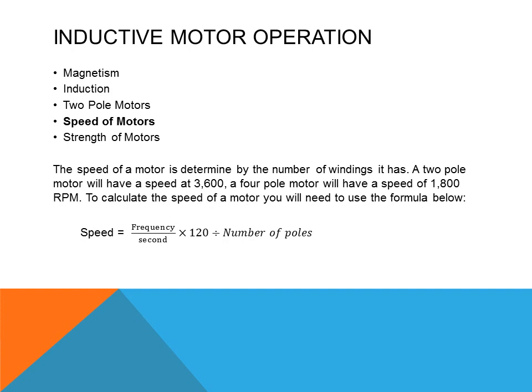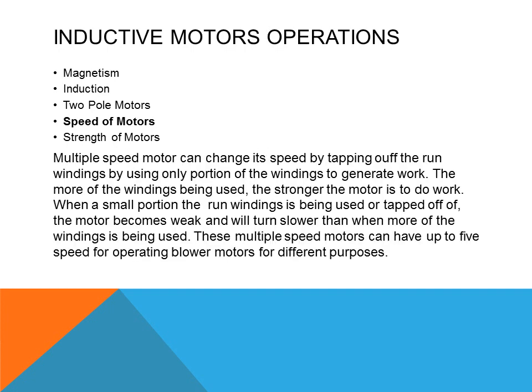The speed of a motor is determined by the number of poles it has. A two-pole motor will have a speed of 3,600 RPM, while a four-pole motor will have a speed of 1,800 RPM. To calculate the speed of a motor, use the formula: speed equals frequency divided by seconds, times 120, divided by the number of poles. Multiple speed motors can change speeds by tapping off the run windings — using only a portion of the windings to generate work. The more windings being used, the stronger the motor; when a small portion is tapped off, the motor becomes weaker and turns slower.